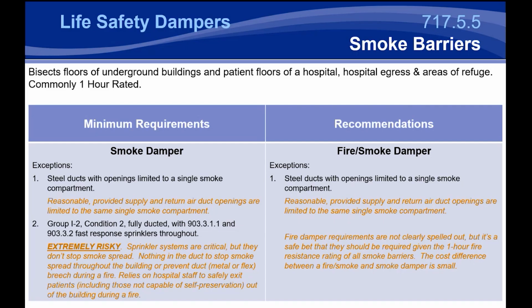For the most part, this is very reasonable. Now, what happened in 2012 is for Group I2 Condition 2 occupancies, the allowable smoke compartment was greatly expanded. And as long as you had a fast response sprinkler system throughout the building, where the fire would be put out very quickly, you could remove the smoke damper requirements through a lot of the barriers in these occupancies. What this turned into is a very large smoke compartment that was actually bisected by fire rated barriers.